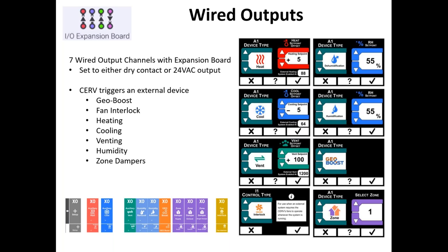The wired outputs then are where the CERV is controlling something externally based on its own configuration. For these, you can control heating or cooling, dehumidification or humidification. We had an article last month on using an inline dehumidifier with the CERV, which would be controlled through an output channel. Ventilation, external ventilation devices. GeoBoost is a preconditioning ground loop exchanger, so that circulation pump would be controlled through an output channel.